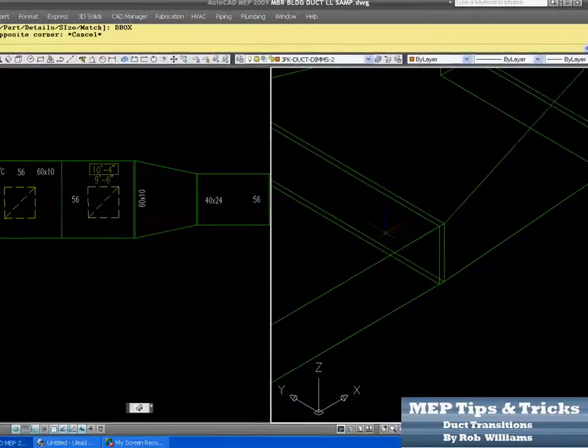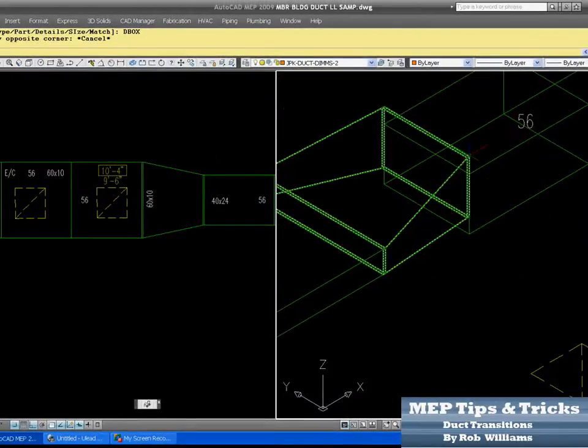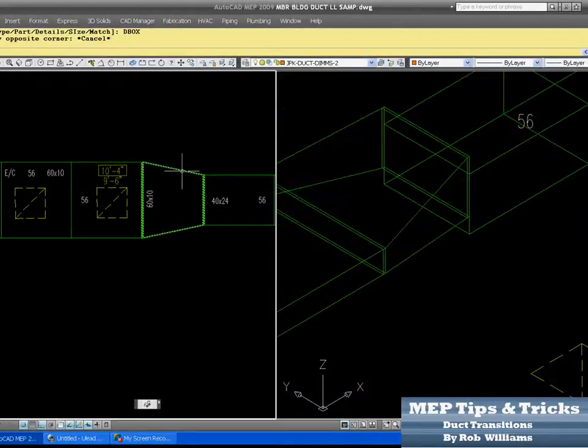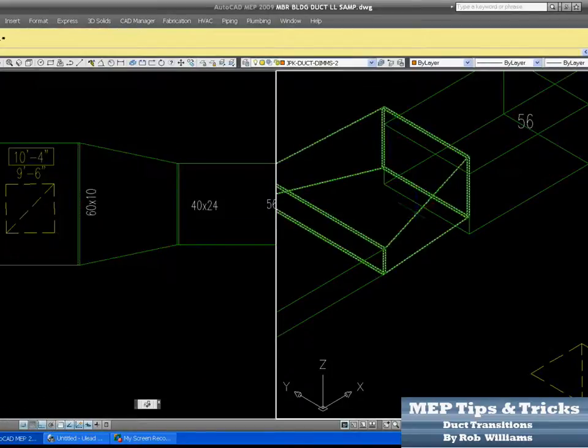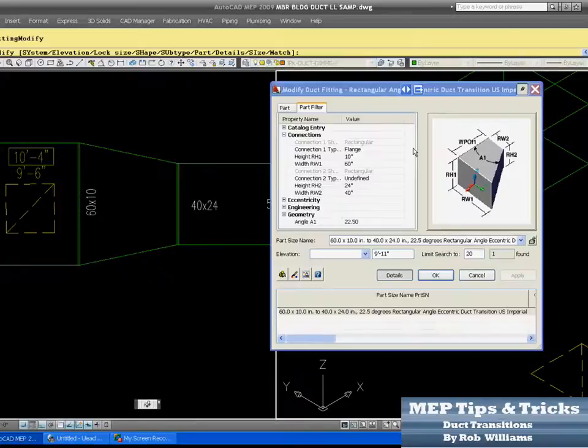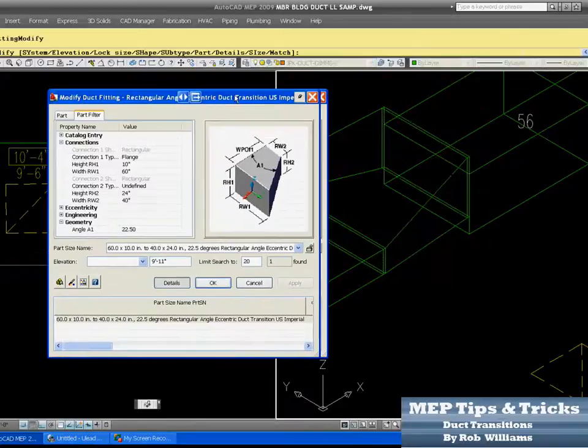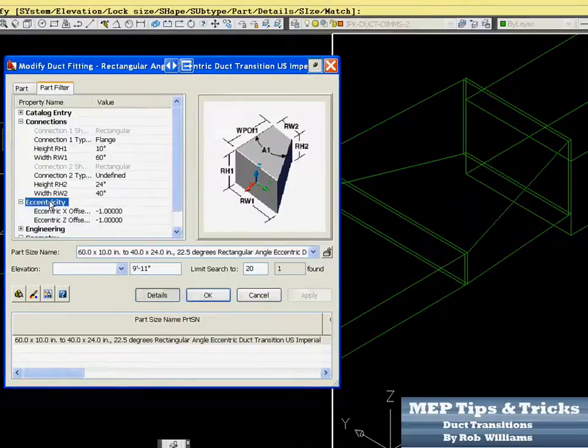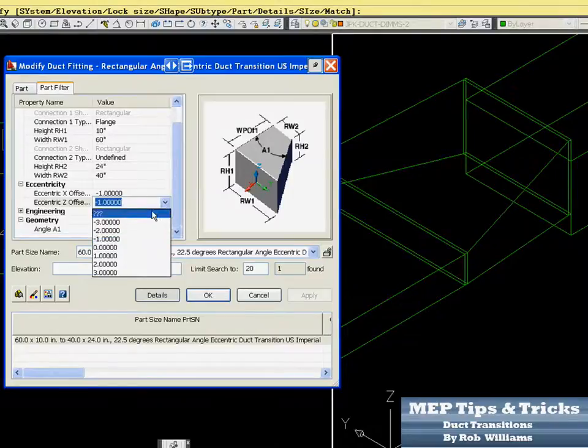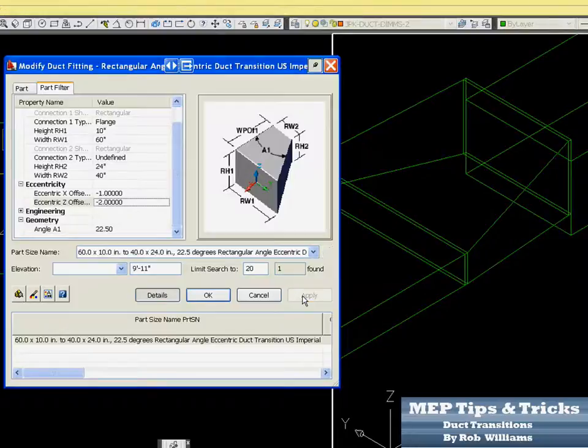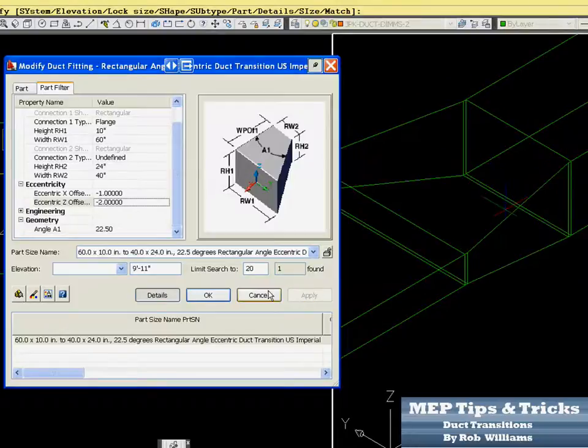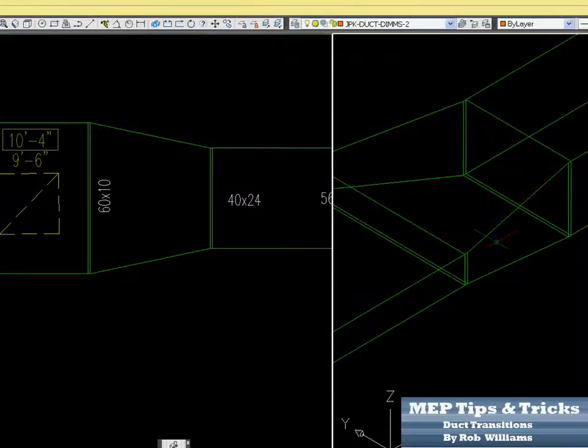And we're going to click okay. Look at it from here. So now we're not flat on top yet, but we've got the length right. So now we're going to come in here and we'll go modify duct fitting. And drag this out of the way. And we want to play with this in the Z. So we come over here and we'll just try a minus two. Click apply. And voila, that works. But it doesn't always work. You may have to tweak it just like you did the other side, or with the angle.